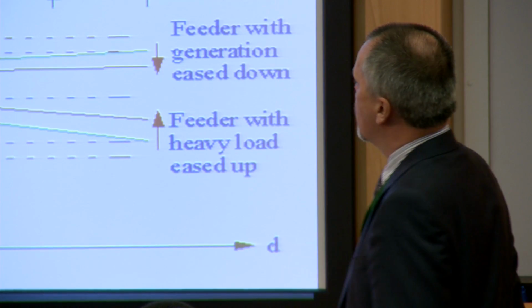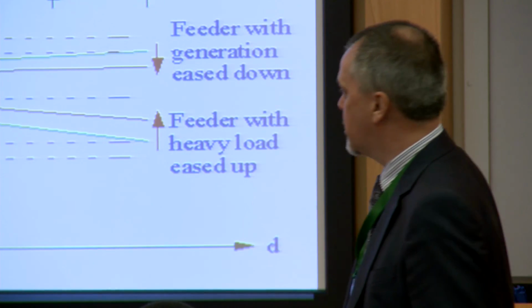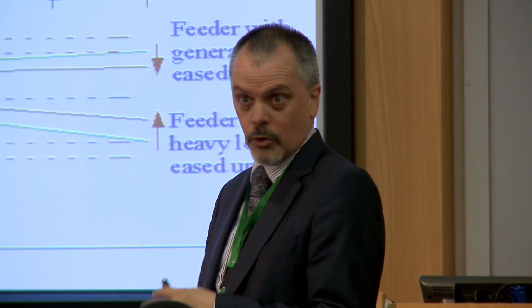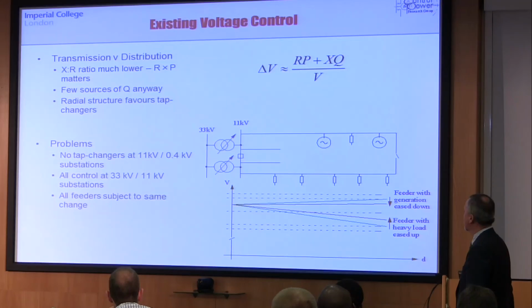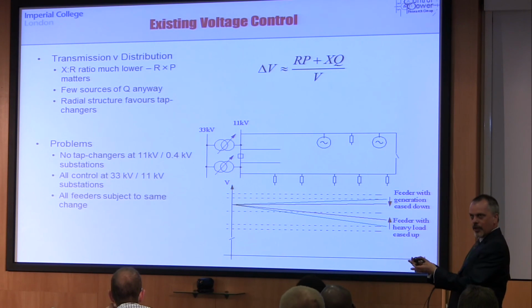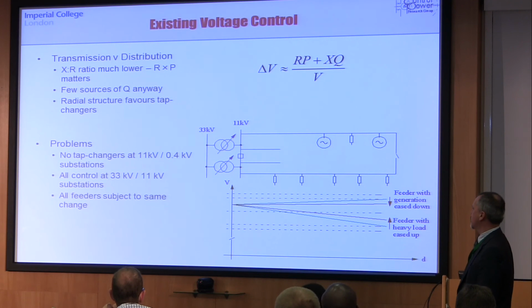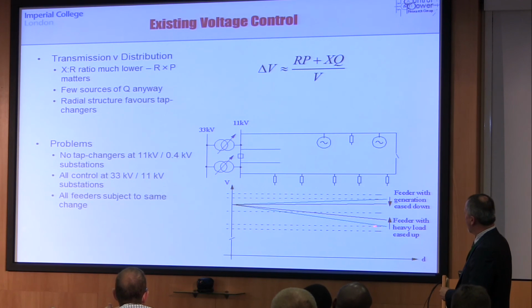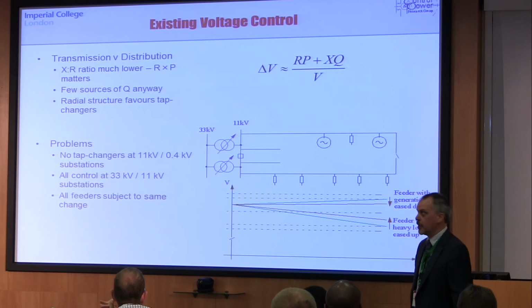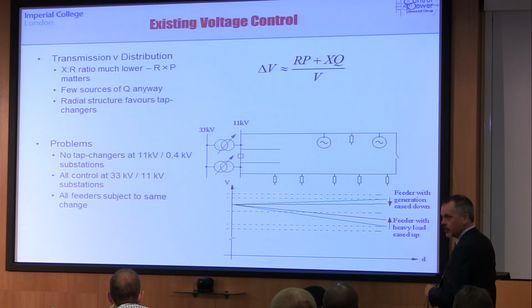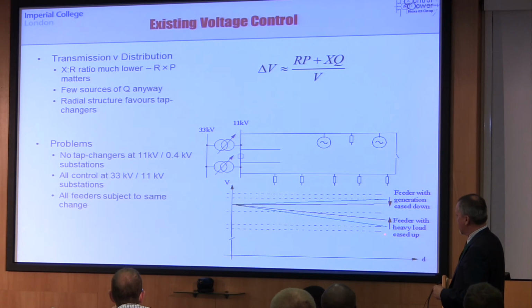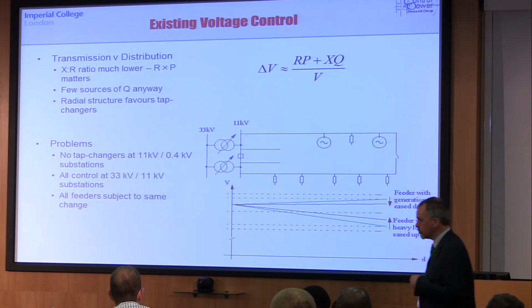But tap change transformers have their problems. First, in UK practice, we only fit them at this level, 33 kV to 11 kV, so we don't use them down the next level at 11 kV to 400 volts, which is where a lot of our problems begin to emerge. And you suffer the problem that all of the feeders on that substation go up or down in voltage together as you change the tap. And if you have one feeder where across the length of the feeder the voltage is falling because of a heavy use of EVs or heat pumps, but you have another feeder with a lot of photovoltaic injection, one feeder up and one feeder down, there's nothing you can do to move this left-hand point up and down with a tap changer that can solve both of those problems together.